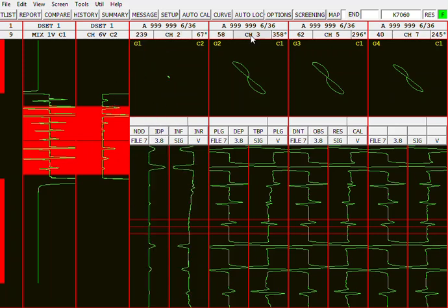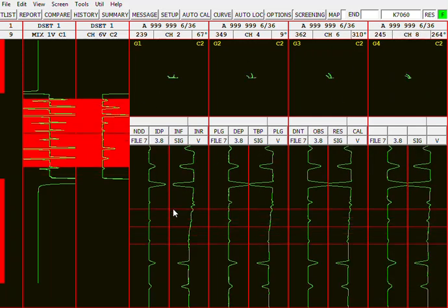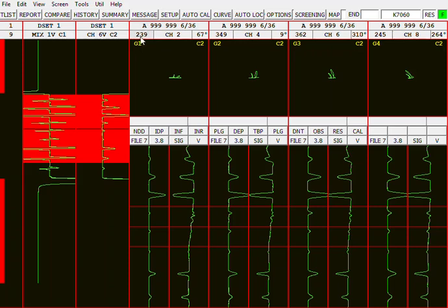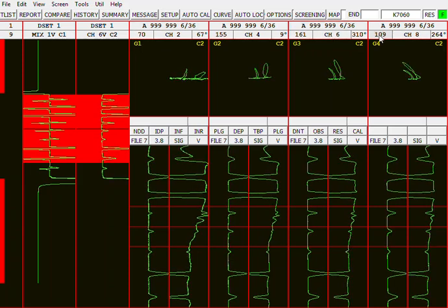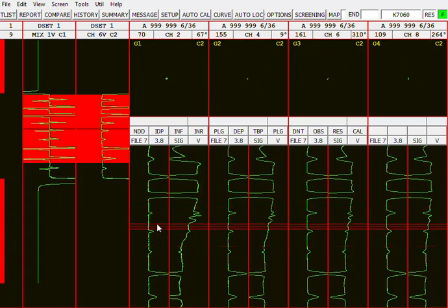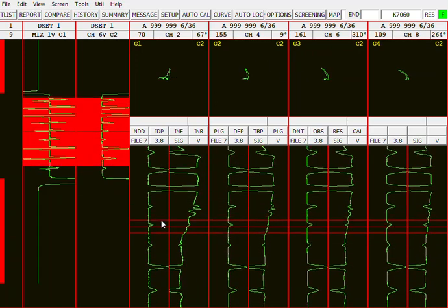Well, if I switch all these Lissajous over to absolute signals like that, my span's kind of low on these, so I've got to crank my span up a little bit so you can see them. Notice how these signals don't have that dual polarity, they just go one direction, up. And this lower frequency, probably about 15 kilohertz, you can detect gradual degradation on this strip chart.